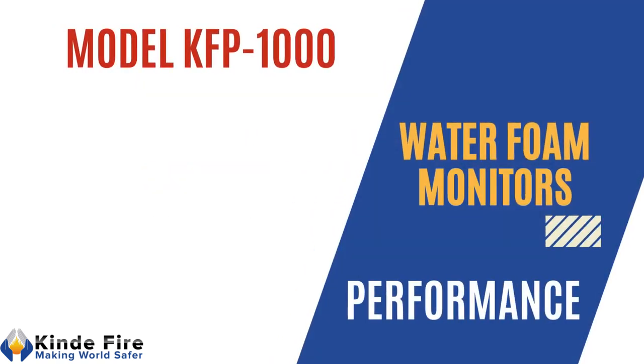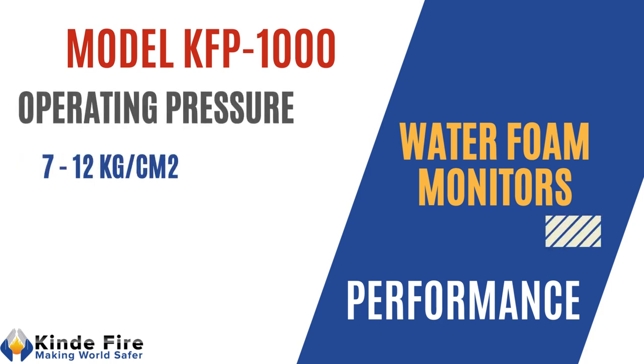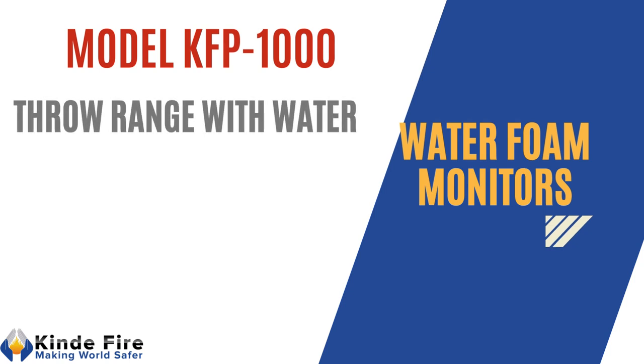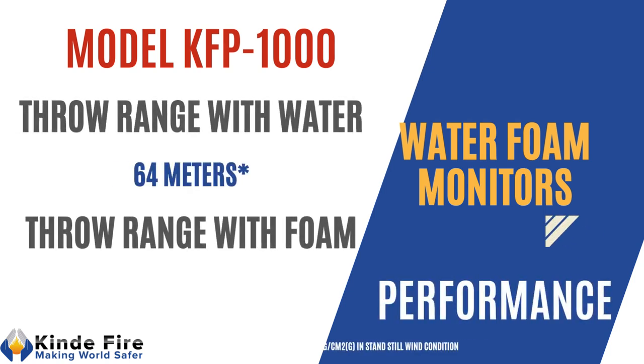Model KFP1000: operation pressure shall range from 7 to 12 kg per cm². Throw range with water shall be minimum 64 m and throw range with foam shall be minimum 60 m.